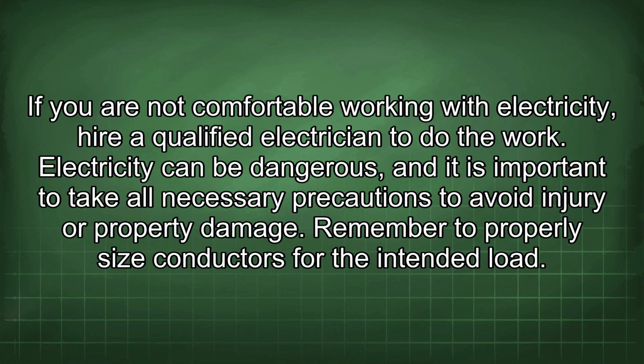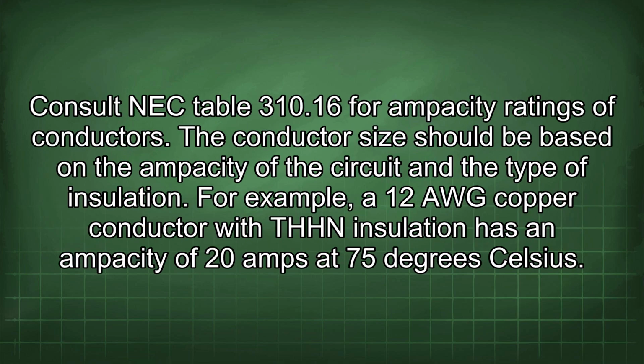Electricity can be dangerous, and it is important to take all necessary precautions to avoid injury or property damage. Remember to properly size conductors for the intended load. Consult NEC Table 310.16 for ampacity ratings of conductors. The conductor size should be based on the ampacity of the circuit and the type of insulation. For example, a 12 AWG copper conductor with THHN insulation has an ampacity of 20 amps at 75 degrees Celsius.